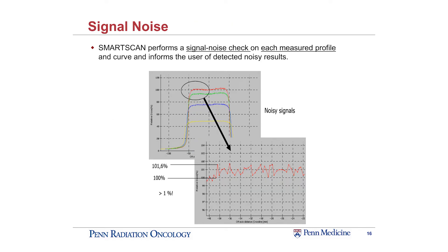The signal noise check is also something that's done in the background as you continually scan. It measures for each profile and curve what the noise is. I've always done a visual check as it's scanning, but this is a quantitative check. There's actually a number that you can either use the default from IBA, or input your own that you determine as a clinic. If it gets noisy, it'll prompt you that it's getting too noisy and to check what's going on. This is a good check so you get quality data that requires minimal processing after you're done scanning.